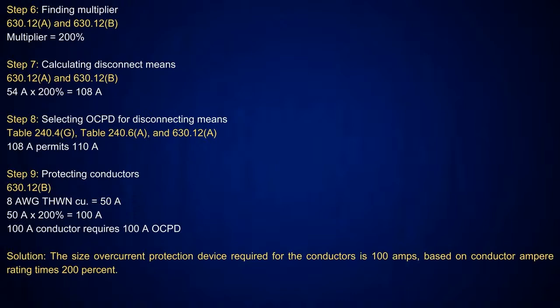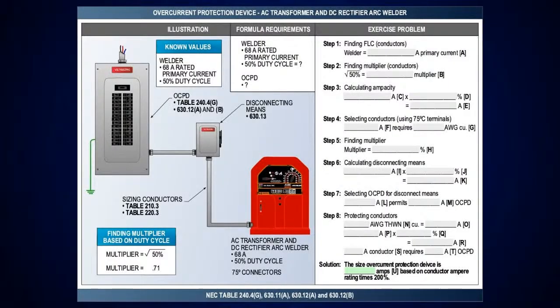So I cross-check myself, and I could have just dropped down because I did go at the 200%, but I just went up to 110 amps just to sort of show you. A lot of people will say, I'm going to go up to 110, but really, would I be able to go down to 100 amps like it's saying not to exceed it? Well, sure, because I just put 50 amps on at 200%, gave me 100 amps. Right. So that is a good way of learning here.